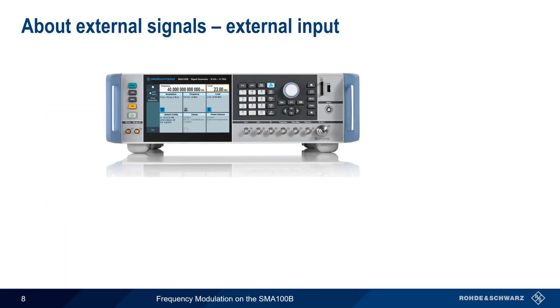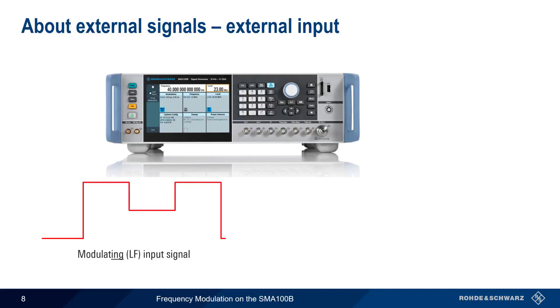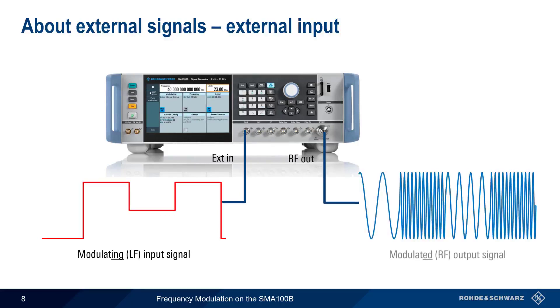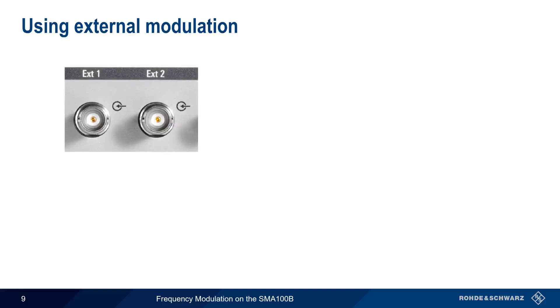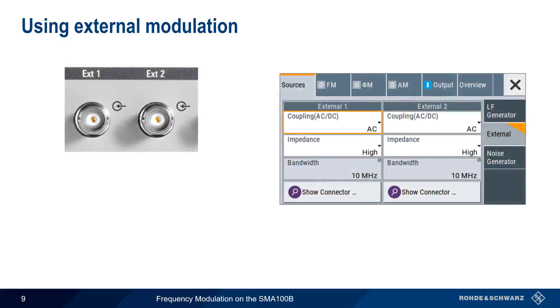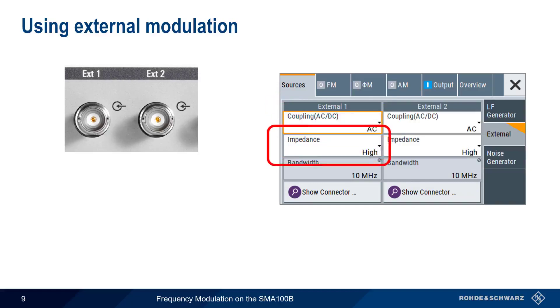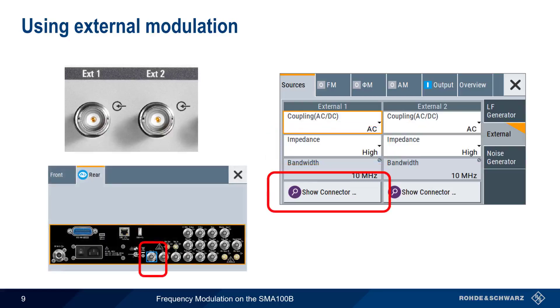In addition to using the internal LF generator, another way the SMA can generate frequency modulated signals is by using an external low-frequency signal as the modulation source. This external source is then used by the SMA to create the modulated RF output. In this case, the input or modulating waveform does not need to be regular or periodic. The SMA has two connectors for external modulation sources: external 1 and external 2. For each external connector, we can specify the coupling — AC or DC — as well as the impedance. If you're unsure about which connector to use, the Show Connector button will open up a graphical view of the SMA with the corresponding connector highlighted.